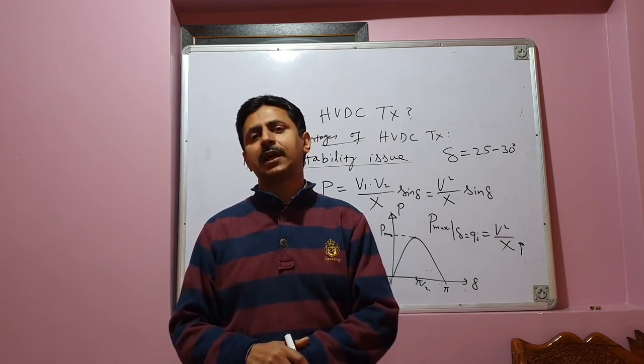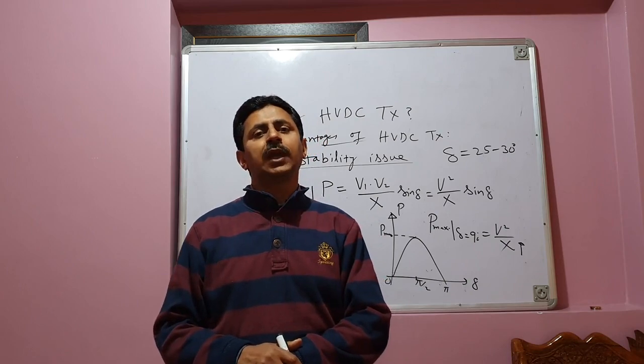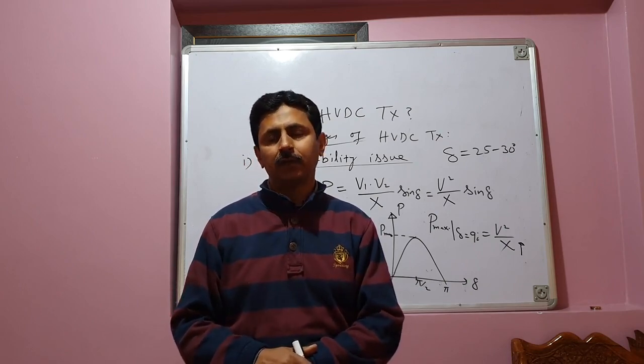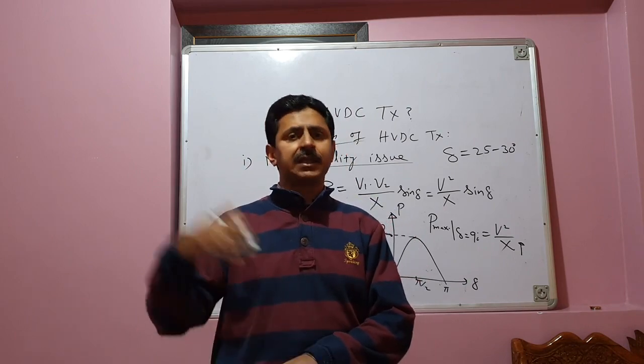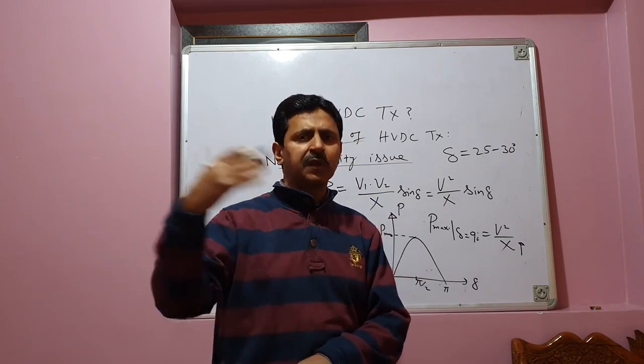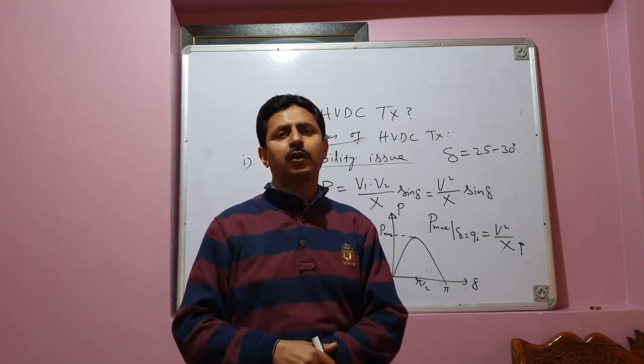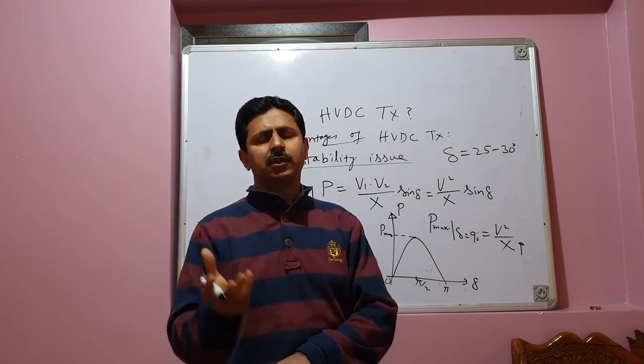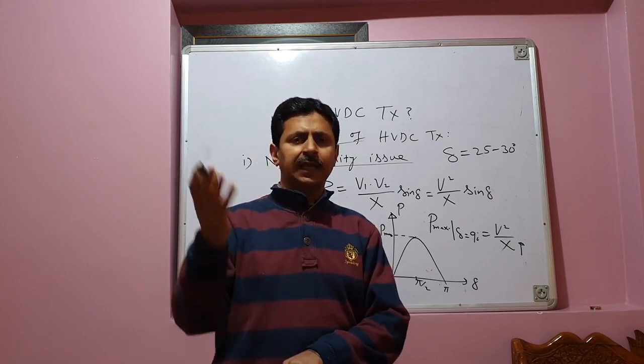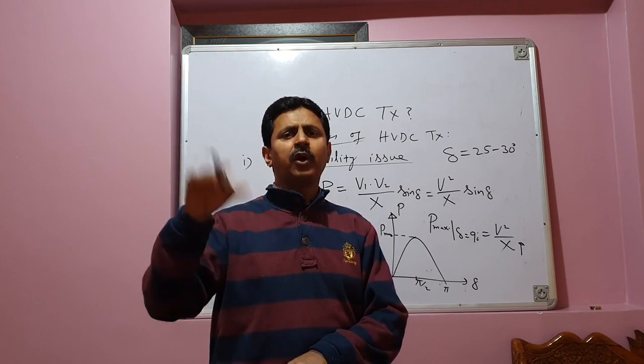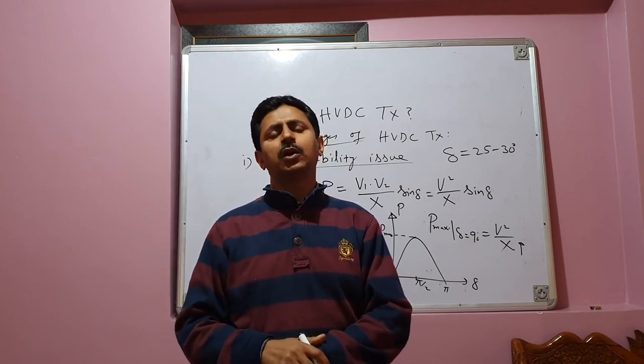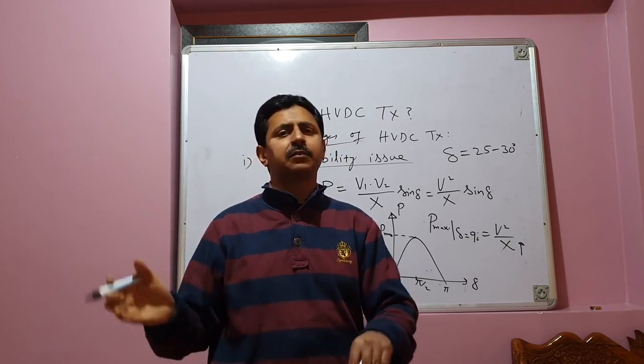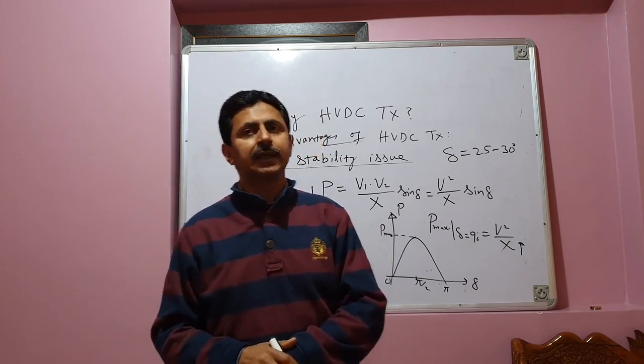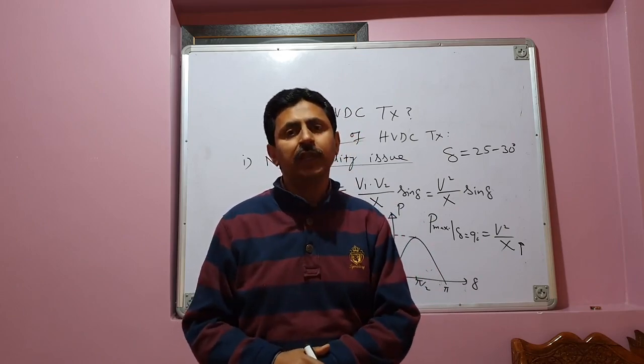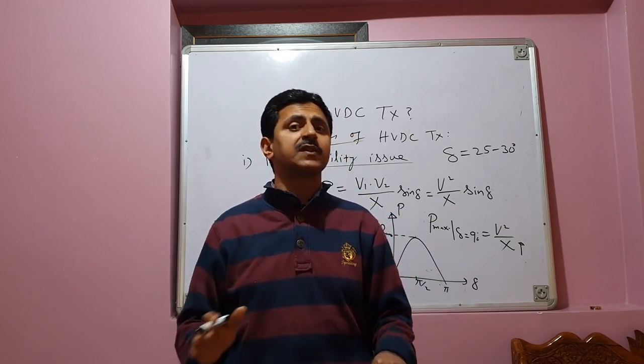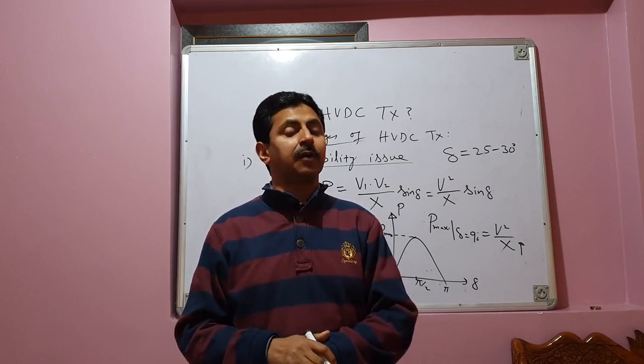And another point is that since stability issue is not there, you can load the line up to its thermal limit. What does thermal limit mean? Until the line burns, because when you transmit the power over the line, there are I square R losses. And because of these I square R losses, the line can heat up, and you can keep on increasing the transmission of power over this DC line until it burns. We will never, of course, do that, which means that we can load the line fully up to its thermal limit. And it is not possible to load an AC transmission line up to its thermal limit because of the stability constraint, stability issue.